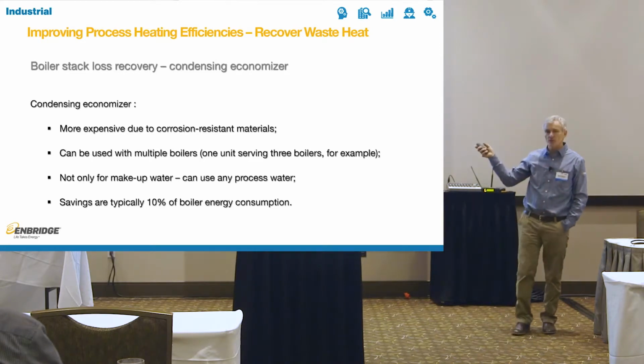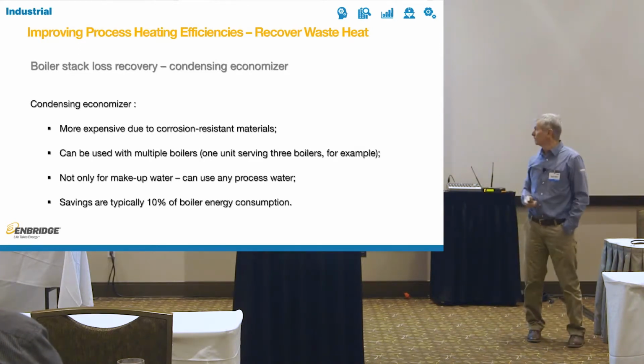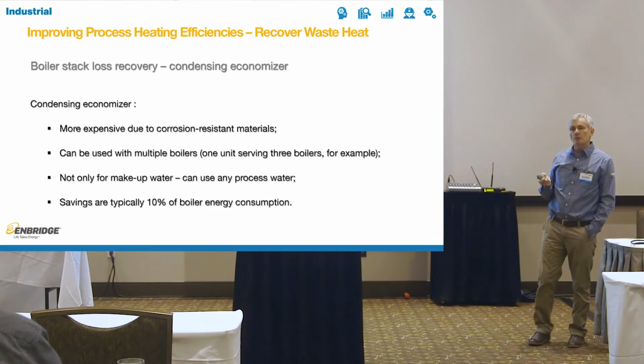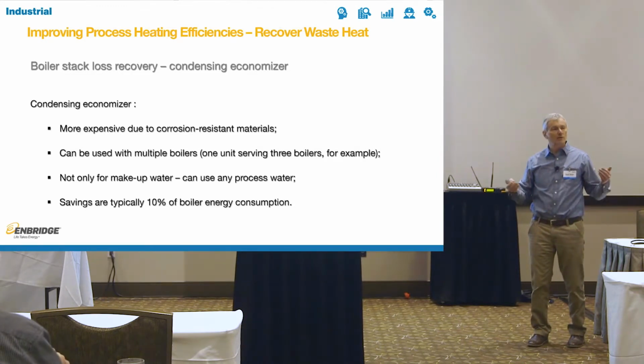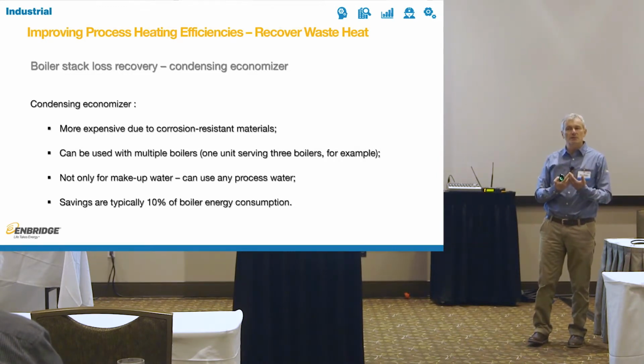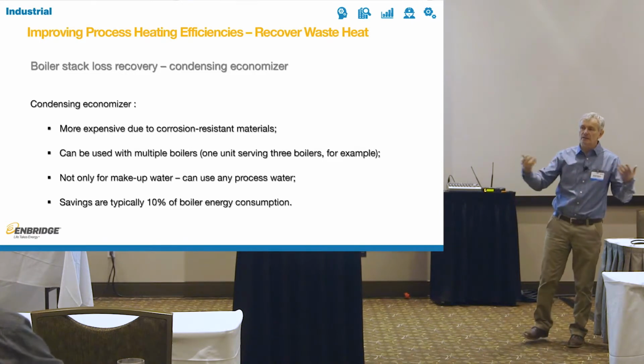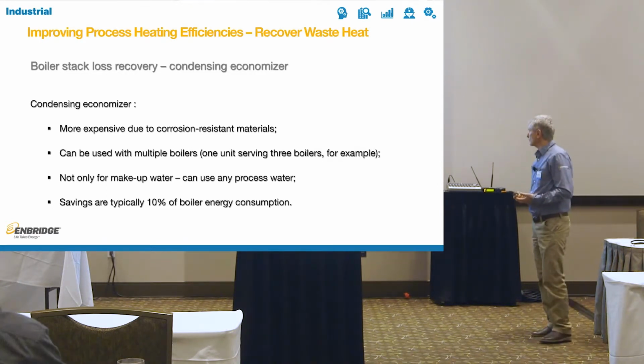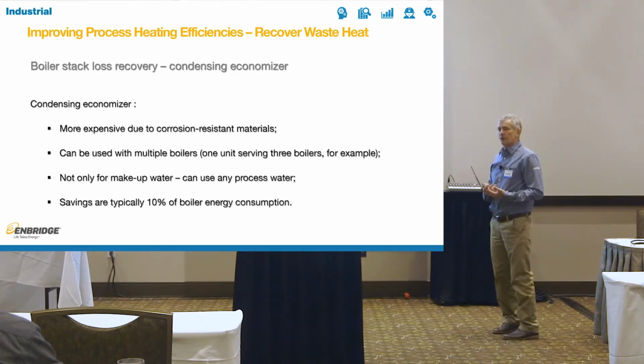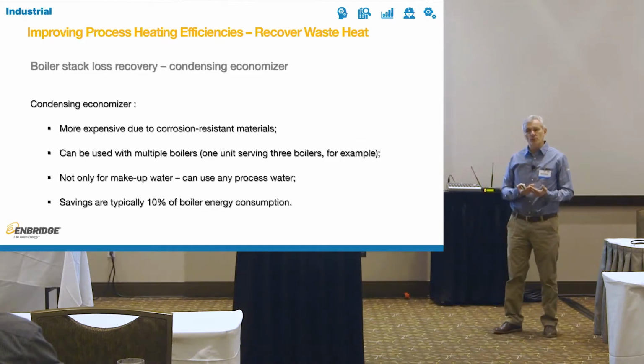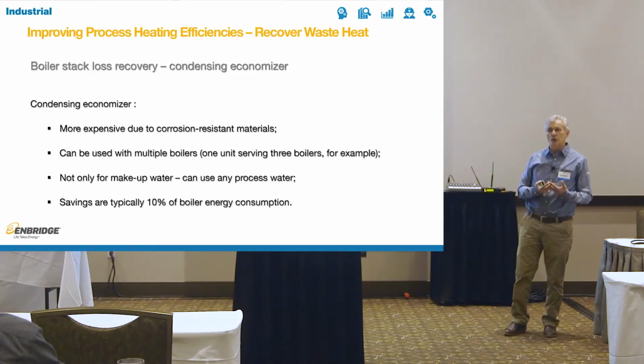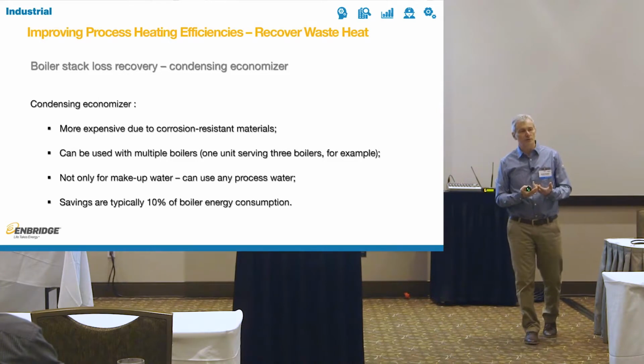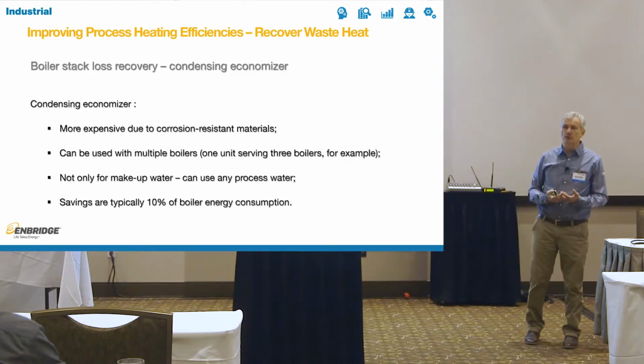So condensing economizer, it's more expensive to implement, yes, but it can be used with multiple boilers. So you can feed 2 or 3 boilers into the same condensing economizer, which means that you don't have to pay 3 times for the same equipment. And it's not for makeup water only. It can be used for your process water requirements. And if you use a lot of warm process water, this is a great opportunity to save.